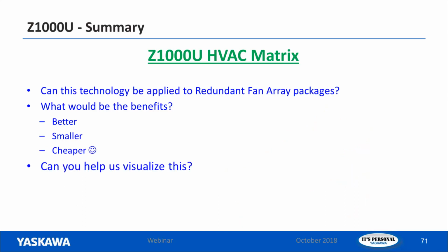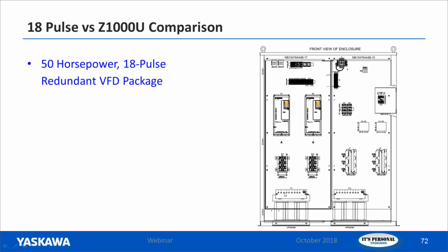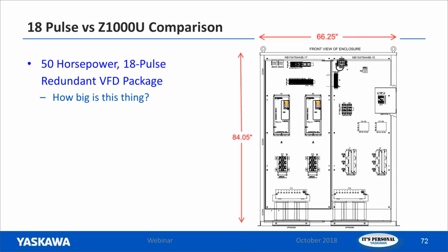So let's take a look at what this looks like. We're going to do this one more time. Over here on the right, we've got a 50 horsepower, 18 pulse redundant VFD package. So we've got 50 horse drive, 50 horse drive, 18 pulse transformer, and oh, what's this? Yep, another 18 pulse transformer. When you're doing these multi-pulse inputs on drives on a redundant VFD package, each one has to have its own 18 pulse transformer input. So that puts us into a very large enclosure. How big, you ask? Well, this particular one, 66¼ inches wide and 84 inches high. This is a walk-in closet.